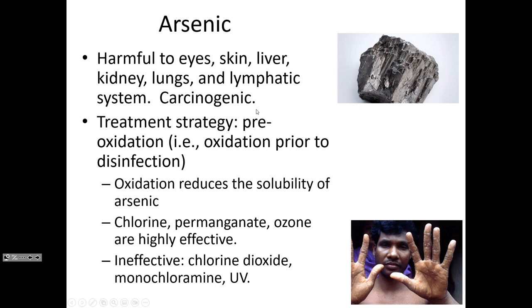Some of the oxidizing agents that are really effective for disinfection don't do anything for arsenic. Chlorine dioxide, monochloramine, and UV are all fine disinfectants for viruses and bacteria, but they don't have enough oxidizing power to take arsenic out of solution.